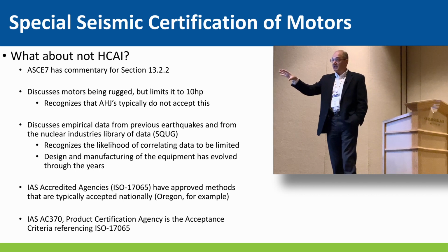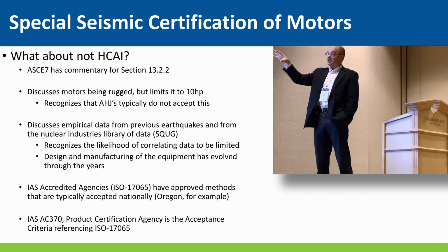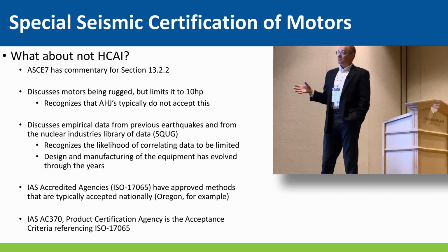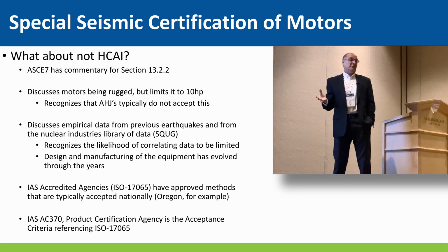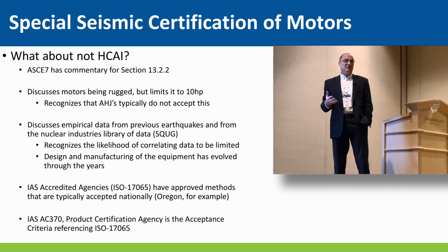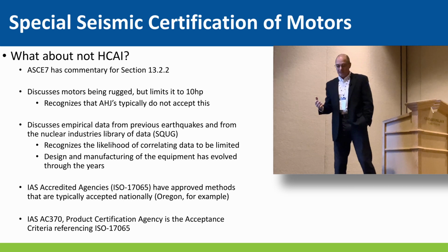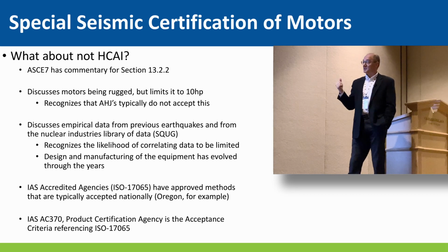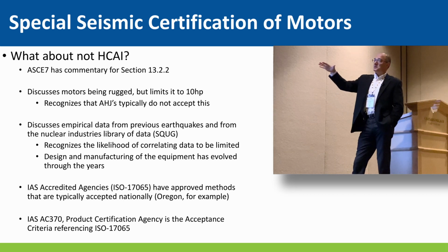There is commentary in ASCE 7 that discusses motors being rugged, but it typically limits it to 10 horsepower. Personally, I think a 200 horsepower motor spinning a 12-inch water pump is also rugged, but the code doesn't believe so.